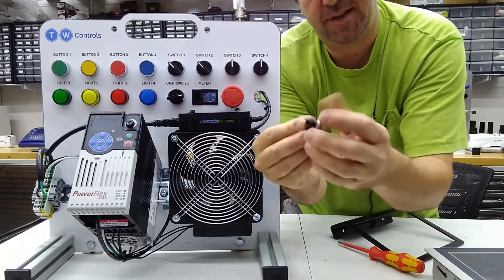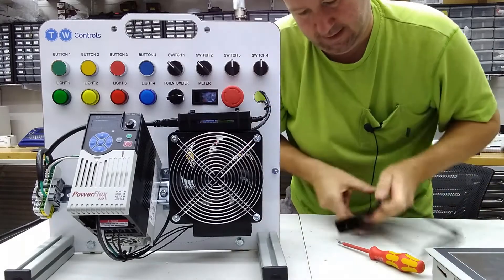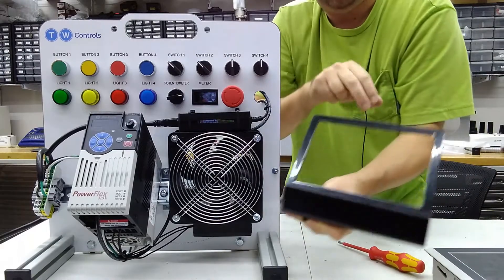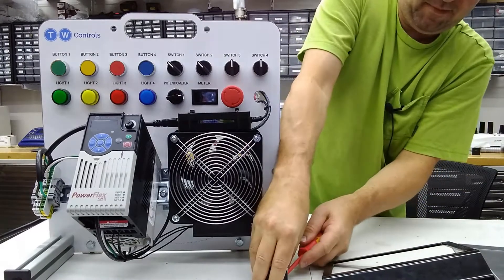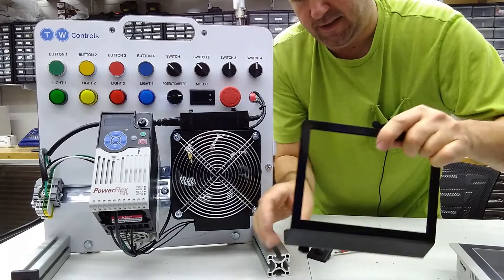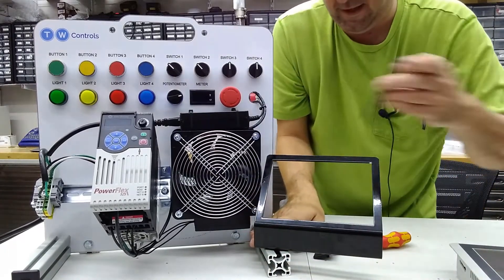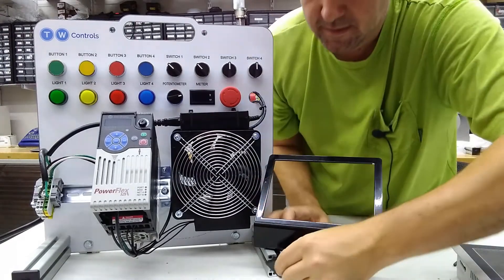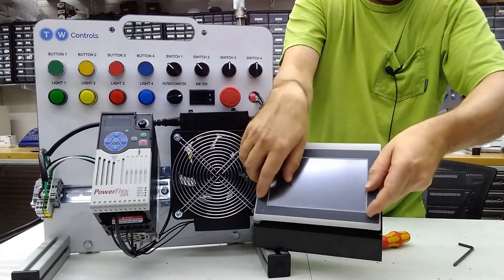What you'll do is take the bolt and the two washers off of the t-nut and then slide it through the hole that would make it mount this way. Just get that started very slightly and pop this end cap off of the end of your trainer right here. Then you can slide this over top of that, and using a four and a half millimeter allen wrench, tighten that back up. Then put your end cap on and you can install your HMI that way.